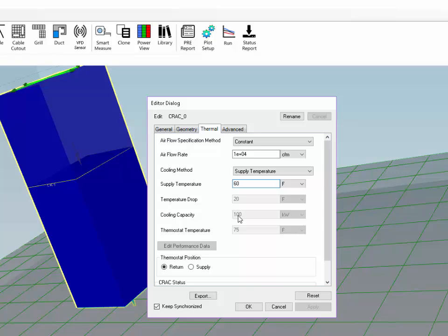So it's a definite indicator there's a problem. But it's a good one, and the way that I do it often is go into the data center, if there's one, if it exists, take a measurement of the cold air coming out of the supply by lifting a tile and just using an infrared gun or something else to shoot the temperature, get a sample of the temperature, and I set this parameter.